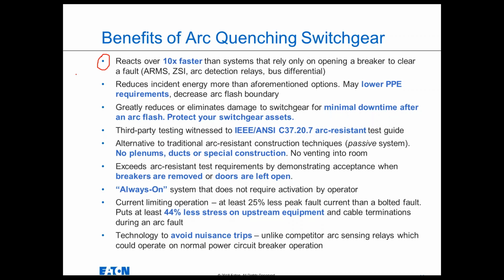So it's not like an energy-reducing maintenance switch where you need to train your people to turn it on when maintenance is being performed on the equipment or downstream of the equipment, and then remember to turn the system back off when maintenance is done. Otherwise, you may risk nuisance operation because the breakers are more sensitive. So, say a motor starting, some large inrush current could potentially cause a nuisance operation. That is not a risk with our quenching switchgear. It's an always-on system. There is no switch to turn it on and off. It's always protecting the switchgear, and it has no effect on the coordination of the circuit breakers. It operates completely independently, and so you'd coordinate the system as you would even without the system, and it just sort of operates on a different plane and has no effect on the coordination of the breakers.